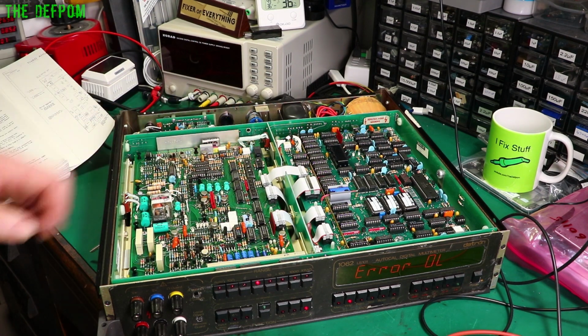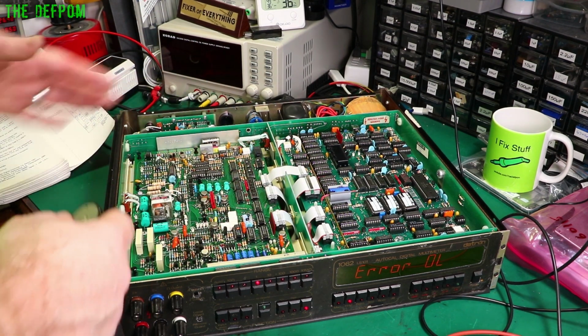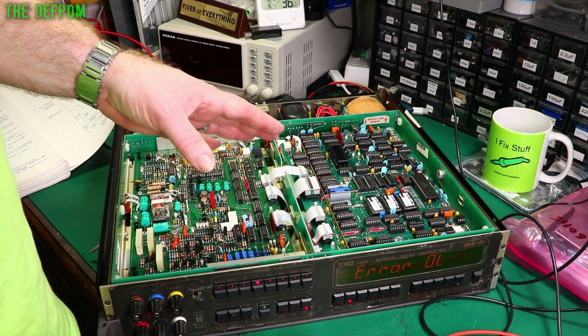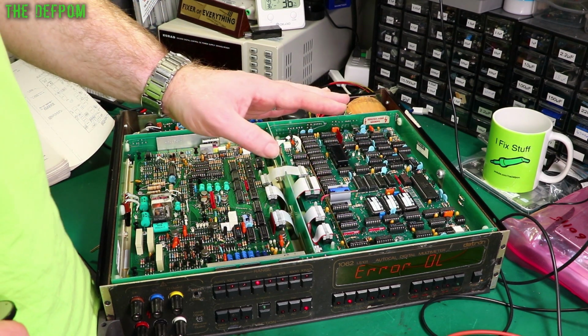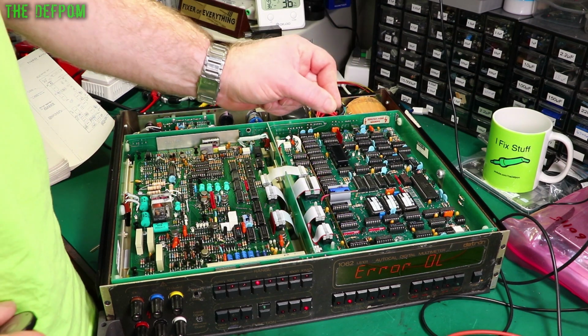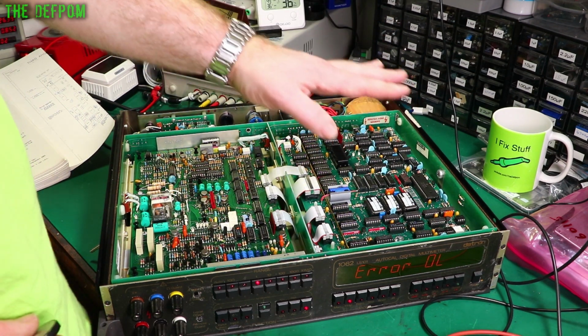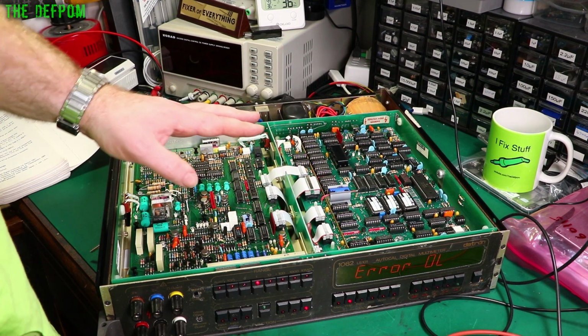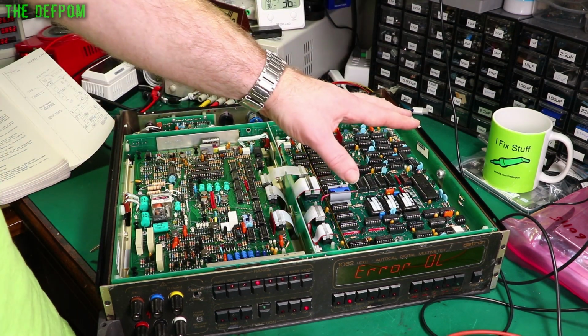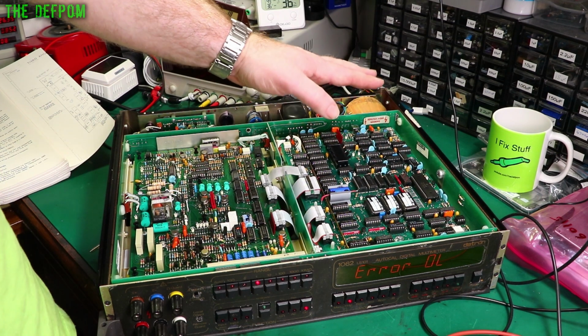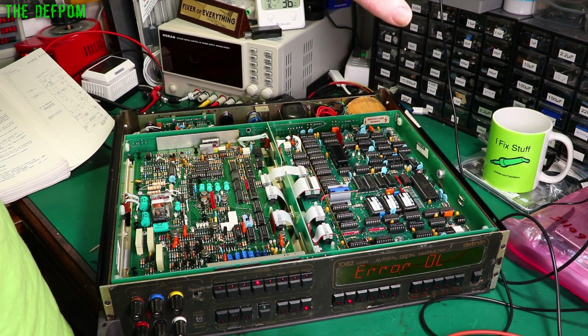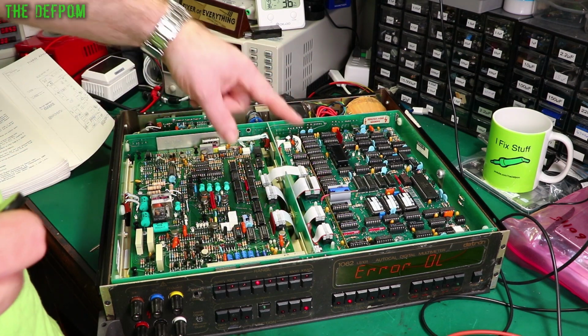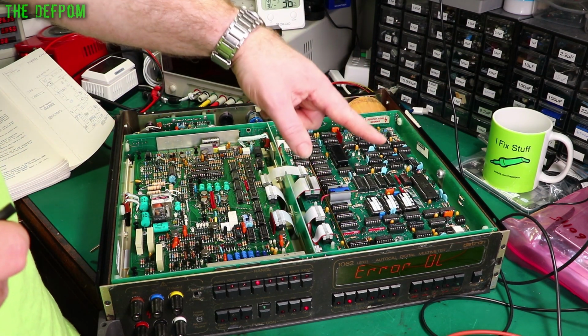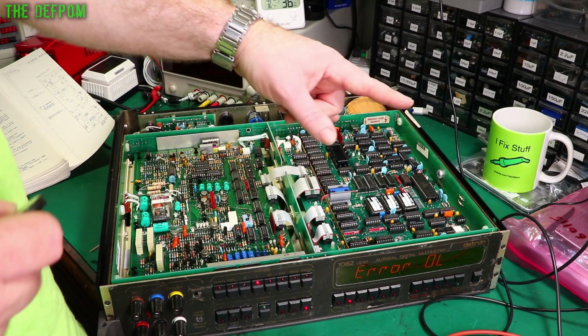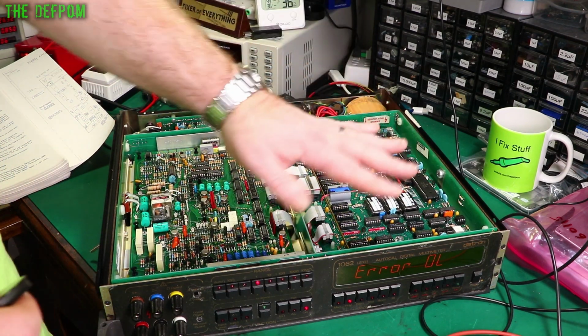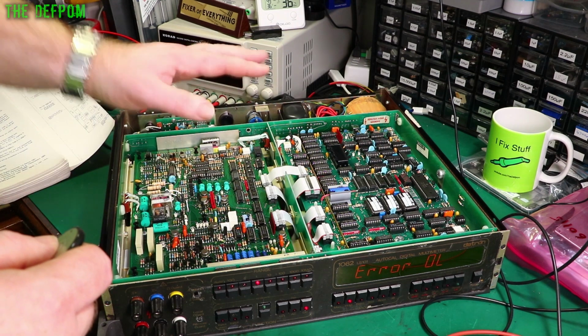Now I need to come over here and look at this board. I should clarify actually. The next step of the digital board is to actually wipe memories. So you wipe the calibration out and start again. Now I don't want to wipe the calibration out. I want to keep the existing calibration intact and then move on and see how close it is at the end. If the digital calibration is wrong, that's fine. I have to wipe it and start again anyway. But I want to see if it's actually okay or not. So although I've done those adjustments, I should be bringing it back to where it should be originally. They won't adjust it by much. We'll see how we go, but hopefully that doesn't actually wipe anything out. But we'll move on to the next board and sort this one out.